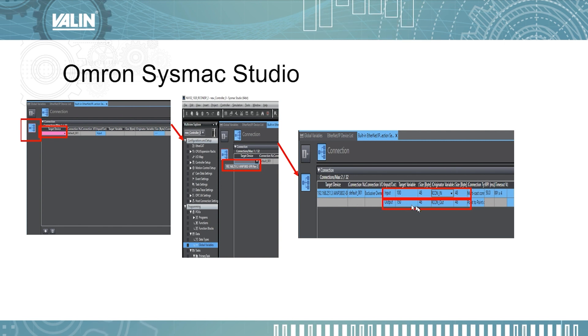A window will show up — click the icon, then click Add. Once done, it will highlight in pink. Select your Archon device at 192.168.251.3. Another icon will come up, and you want to input exactly like this: if your system has two axes, set the Input target variable to 100 and the originating variable to Archon_In. Then set the Output target variable to 150 and the originating variable to Archon_Out.